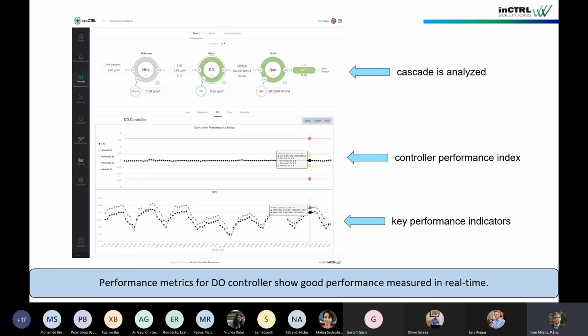We have a running real-time metric of controller performance, an index relative to a reasonably tuned, good PID controller. We can look at various KPIs, key process indicators, that help diagnose what's happening with that performance index. If the index is too high, it might indicate the controller isn't tuned tightly enough and that you might want to retune it.